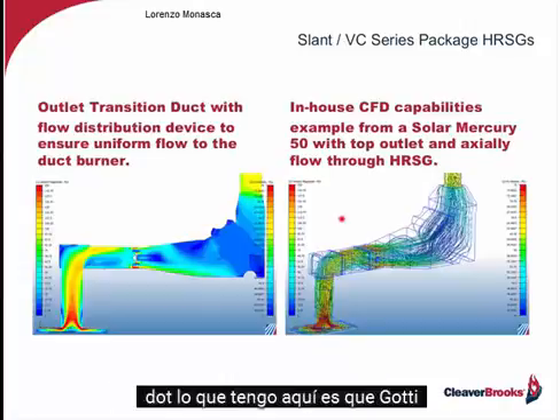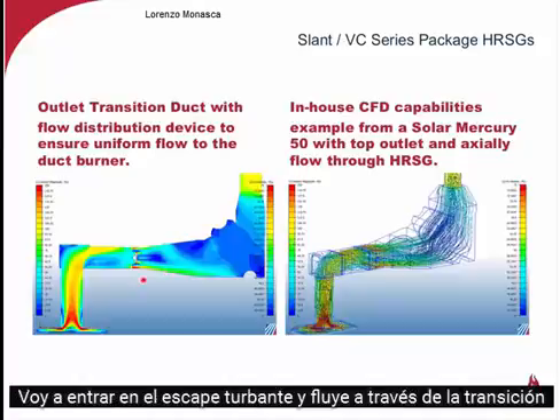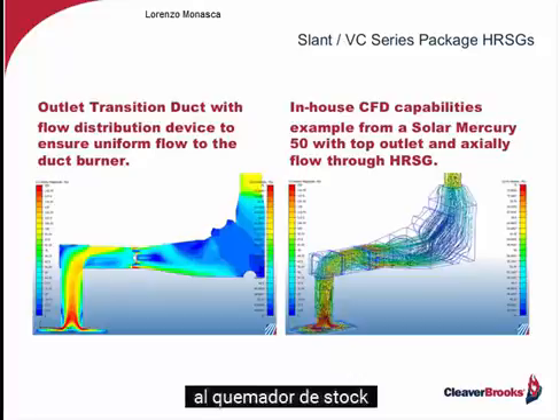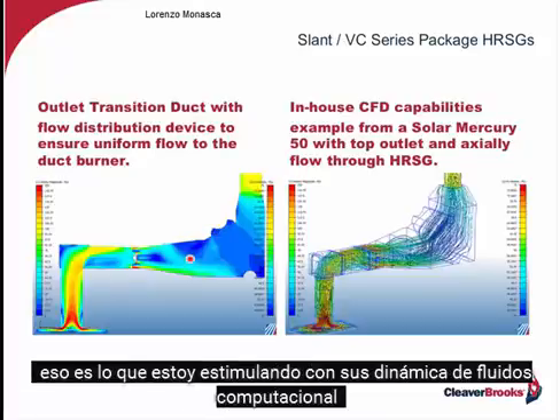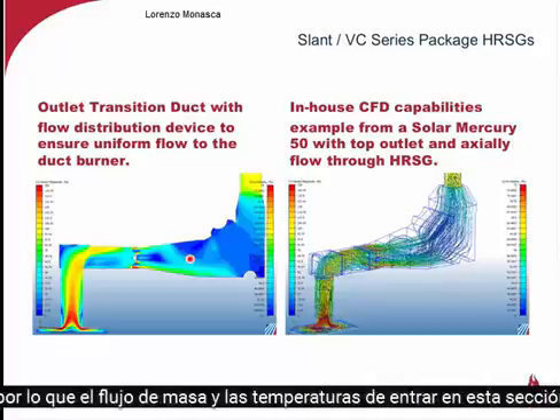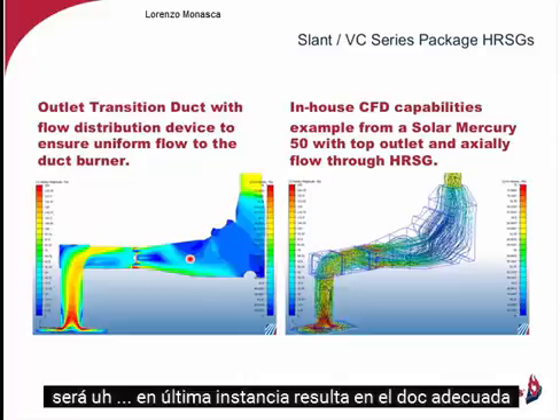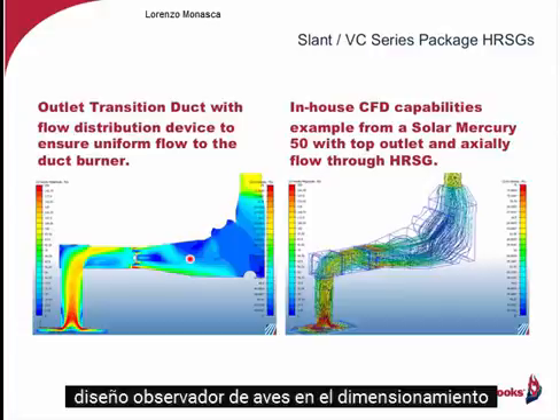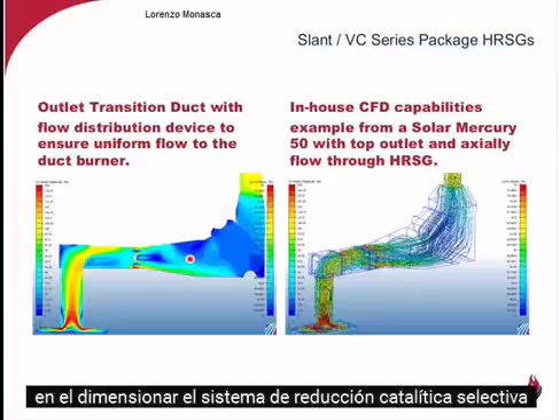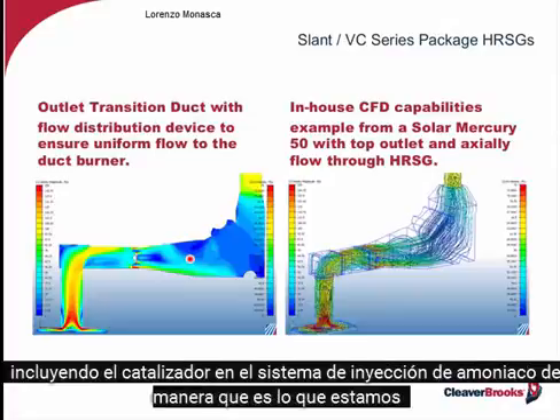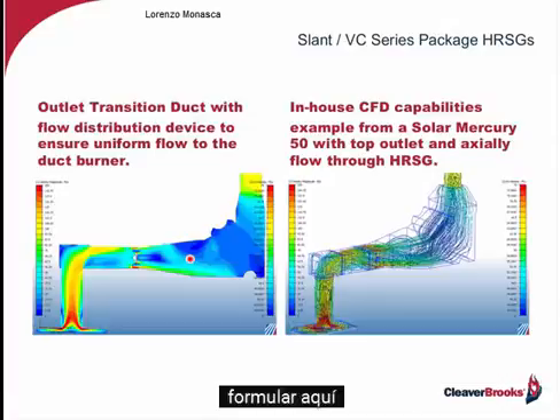So what I've got here is I'm coming in from the turbine exhaust and flowing through the transition ducting to the duct burner. That's what I'm simulating with this computational fluid dynamics. So the mass flow and the temperatures entering this section will ultimately result in the proper duct burner design and the sizing to handle the required load. Now, this information will also be critical in the sizing of the selective catalytic reduction system, including the catalyst and the ammonia injection system. So that's what we're formulating here.